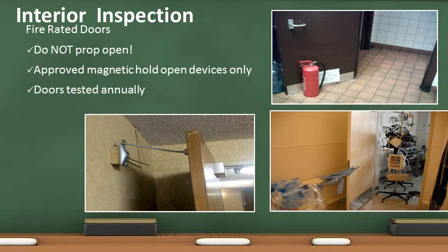When installed with permits and according to code, magnetic door holders may be used to hold fire doors open. When devices detect a fire or smoke, the magnet releases the door and it should close and latch automatically. Magnetic hold-open devices require periodic testing and maintenance. Look closely at the photo on the left. The magnet that is supposed to connect with the hold-open assembly has been hooked to the top, thereby defeating the hold-open device.